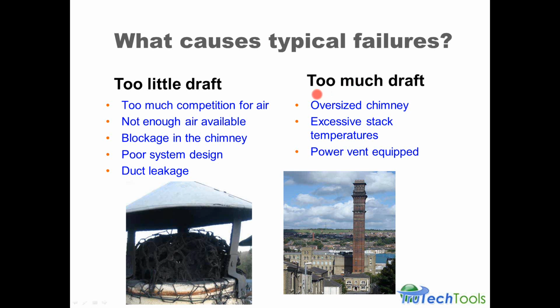Too much draft can be caused by an oversized chimney. It's just moving way too quickly at too high a velocity. Excessive stack temperatures, there's too much buoyancy. Again, it's not designed correctly for the situation. Or if there's a power vent that may be causing too much flow through the system, higher than desired flow.